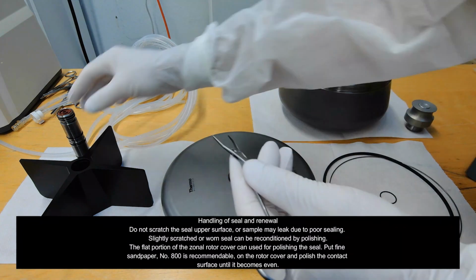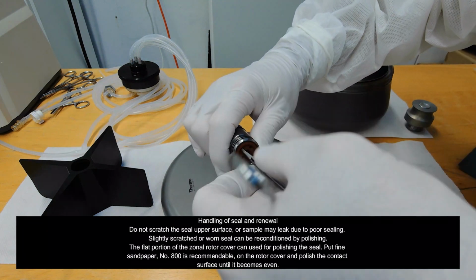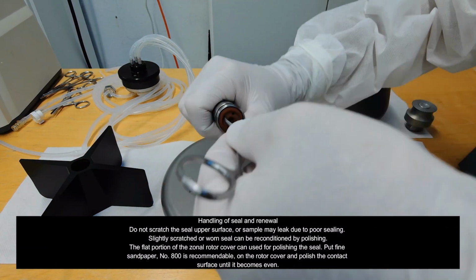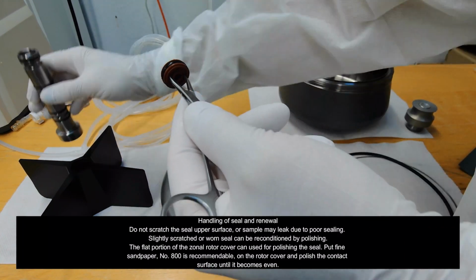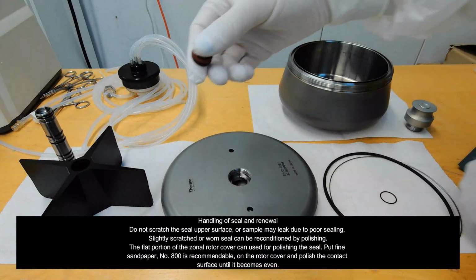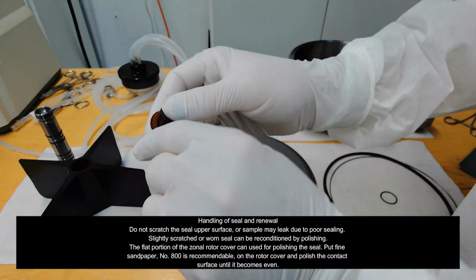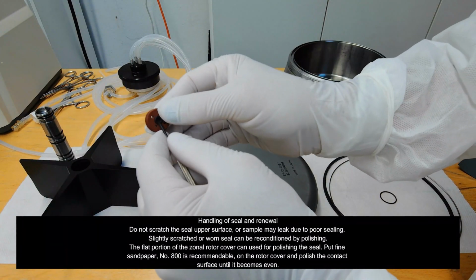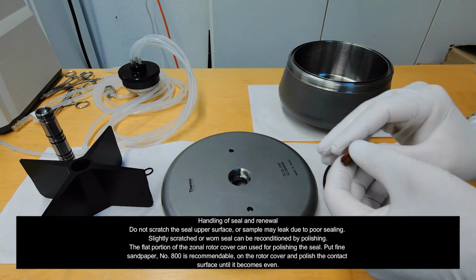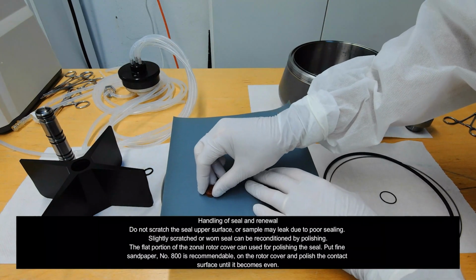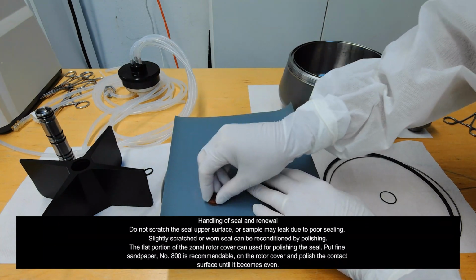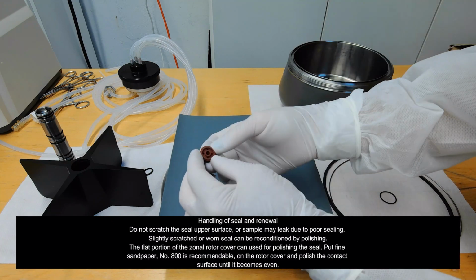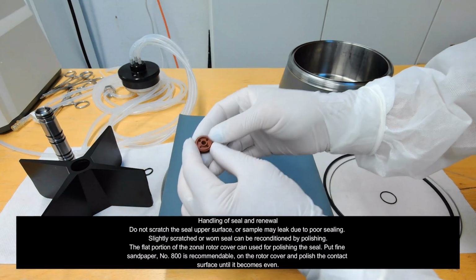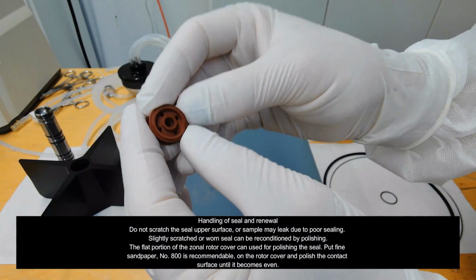Handling of seal and renewal. Do not scratch the seal upper surface or sample may leak due to poor sealing. Slightly scratched or worn seal can be reconditioned by polishing. The flat portion of the zonal rotor cover can be used for polishing the seal. Put fine sandpaper, number 800 is recommendable, on the rotor cover and polish the contact surface until it becomes even.